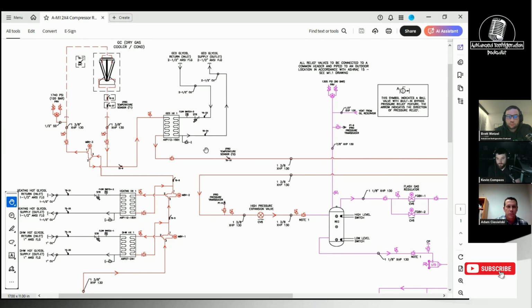But in this situation, it was unique to walk in the rack room and just the compressors are just humming and so quiet and running at nearly a 70-degree condensing temperature because we've got this glycol that is providing that subcooling, and this water glycol coming in the summertime is roughly 60 or 65 degrees. I think we ran transcritical for maybe half a day, and it was because the gas cooler was 100% plugged with cottonwood, and it was about as low as you could get running transcritical. And then as soon as it got cleaned, it was instantly back subcritical. Yep.